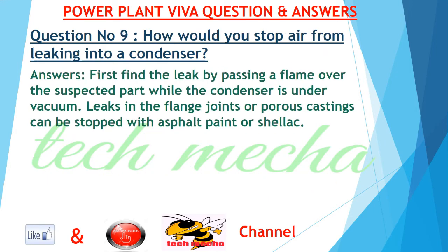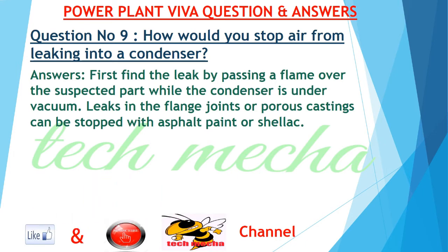Question number 9: How would you stop air from leaking into a condenser? Answer: First, find the leak by passing a flame over the suspected part while the condenser is under vacuum. Leaks in the flange joints or porous castings can be stopped with asphalt paint or shellac.